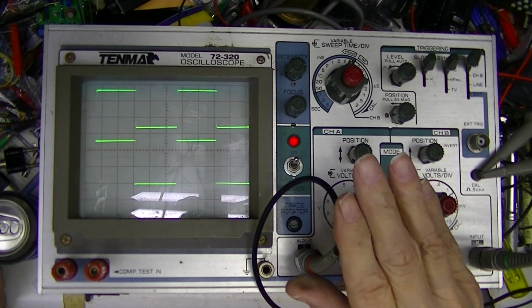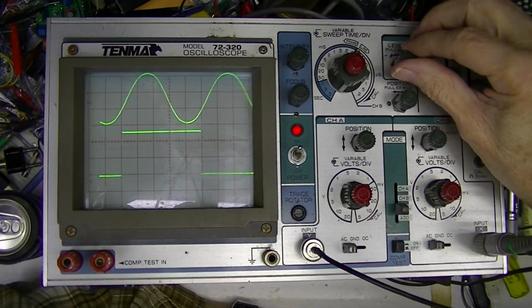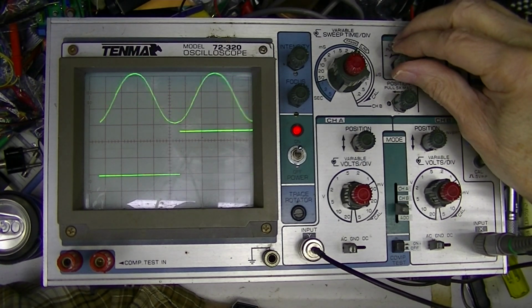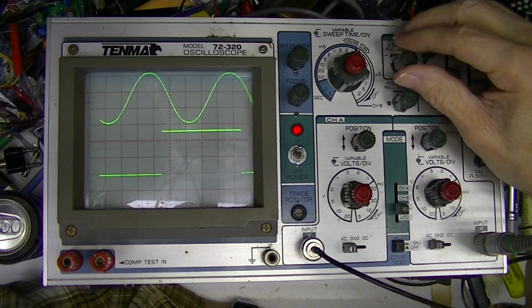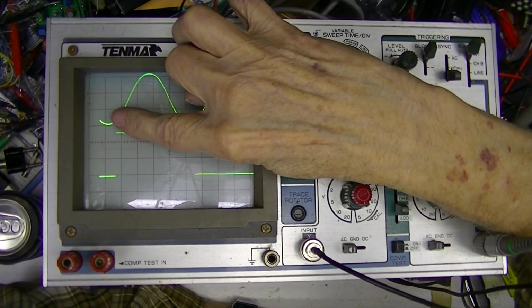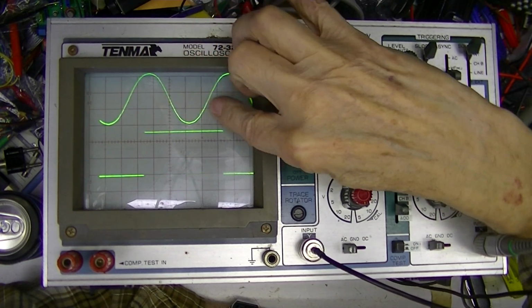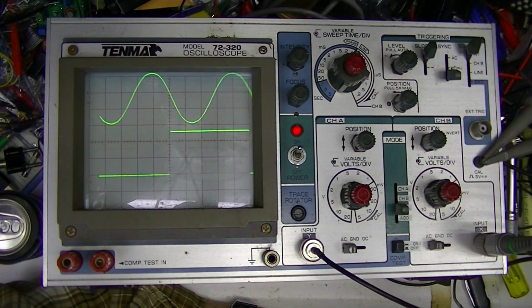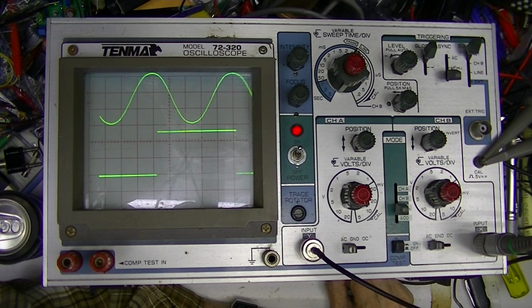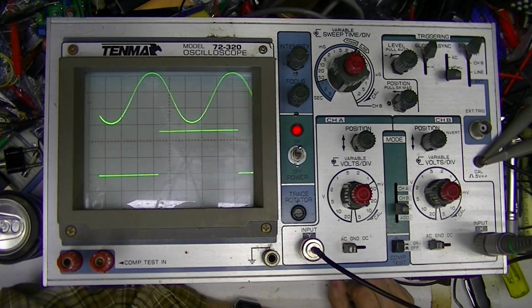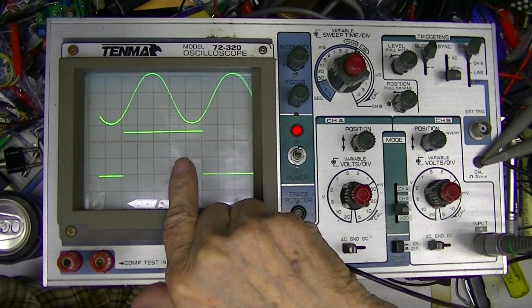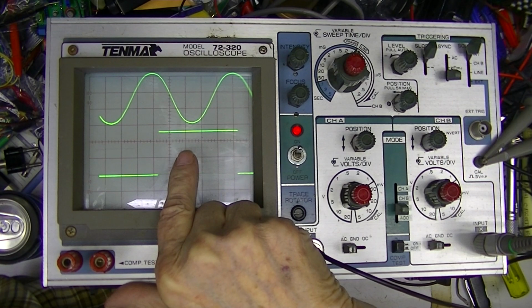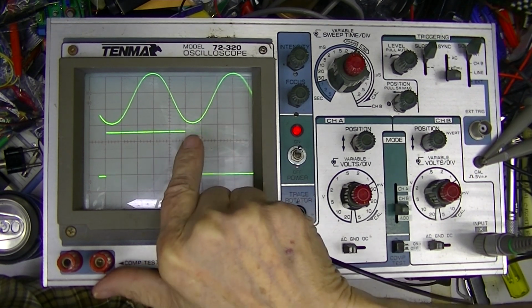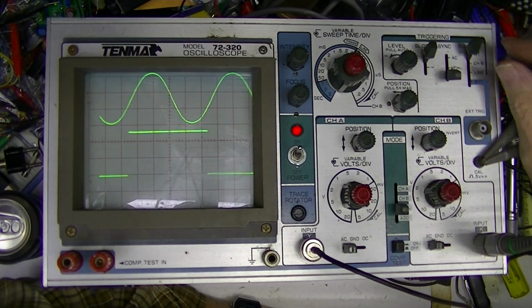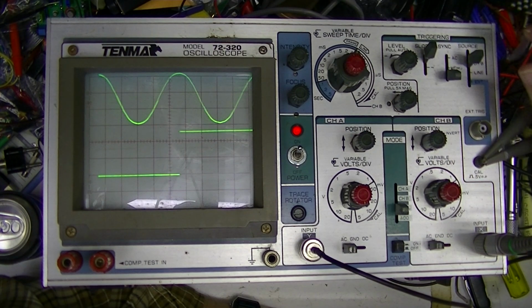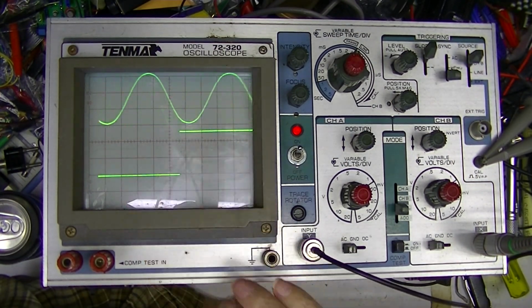Let me hook a sine wave into channel A. Looking at the little line here in the sine wave, that's where we grab the signal and then paint it. But I'm only syncing on channel A. And so channel B is slightly different in frequency from channel A. I can't synchronize both of them at the same time. I can choose to synchronize off channel B. So I'm synchronizing off channel B. Channel A is free running.